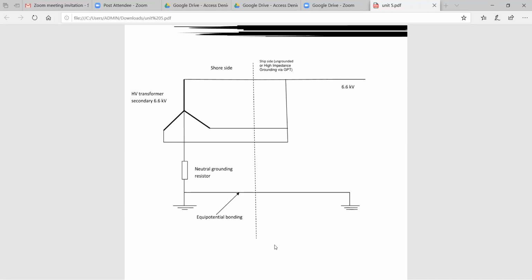Both are interconnected. With an interconnected medium, automatically the two ground systems operate on the ship. The 6.6 kV transformer is on the primary side, that is the shore side, and then the same 6.6 kV system operates on the ship side. So both sides have the same operating voltage level. The neutral grounding resistor can be operated on the shore side as well as the ship side. The system will be connected.